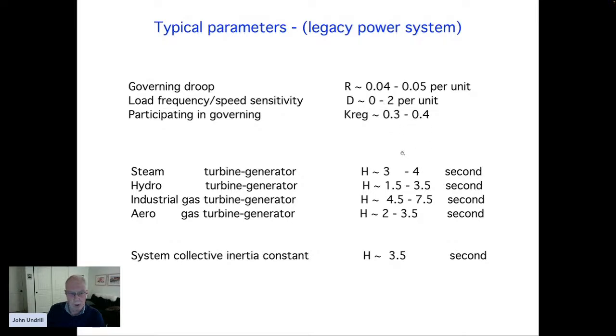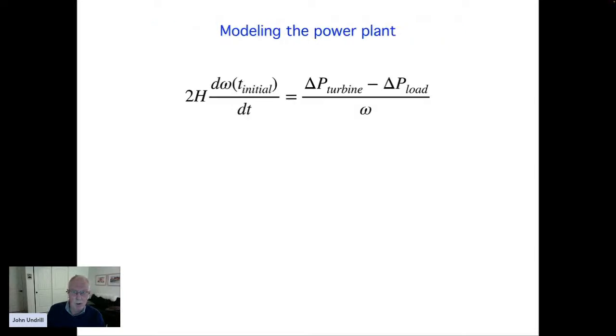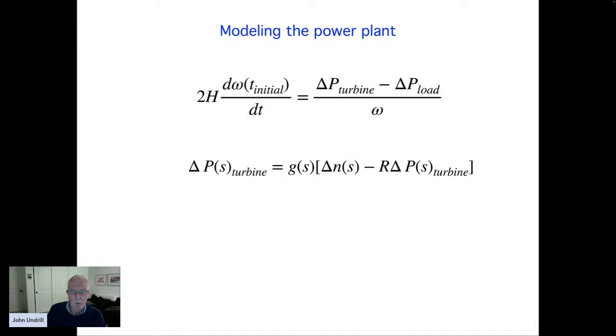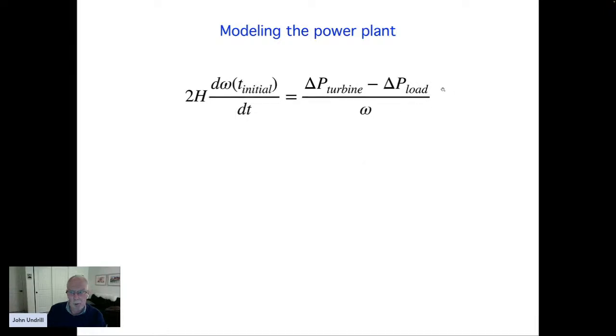I just want to show you our time constants are in the order of seconds. Inertia time constants of the order of 2 to 5 seconds, and the governing fraction: 30% of the plants in the system were contributing to control. So we modeled the power plants and rotating inertia by Newtonian dynamics. We've got to recognize that if I increase the load, I have to increase the turbine power.